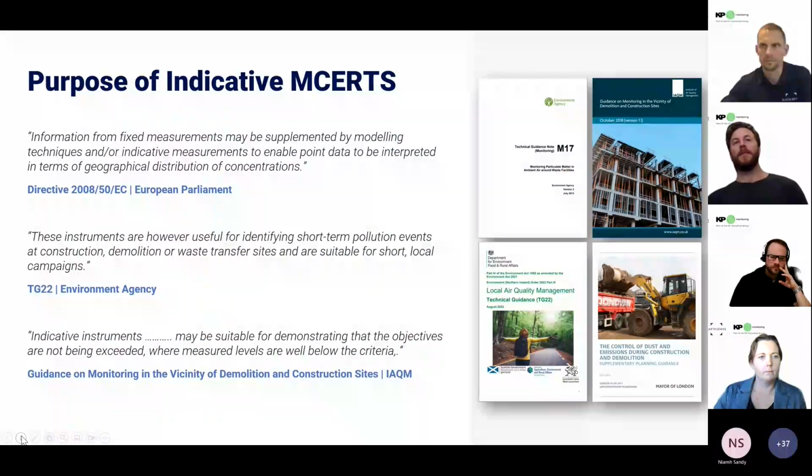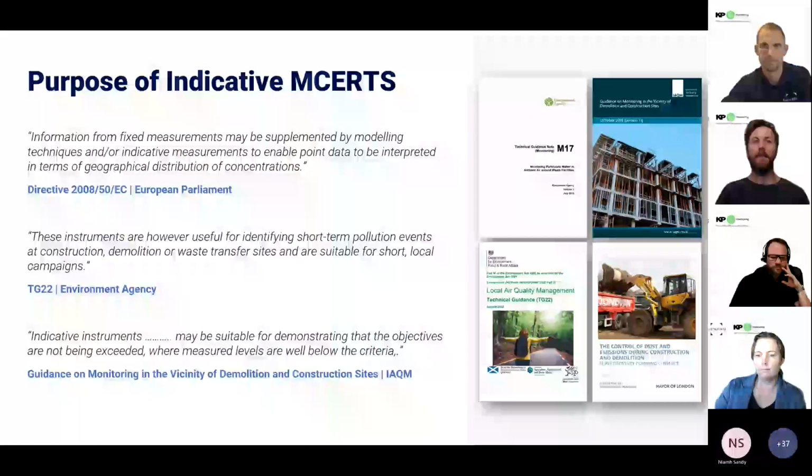So when I looked at the list of people coming today, I feel like everyone probably knows what indicative MCERTS is, but I think just a few bullet points on here. In my mind, indicative MCERTS and the equipment which is covered in it is always going to be for supplementary information. Reference equivalent measurements are there to be used to show compliance against ceiling objectives. Indicative measurements definitely aren't for that. They're there to be supplying supplementary information.